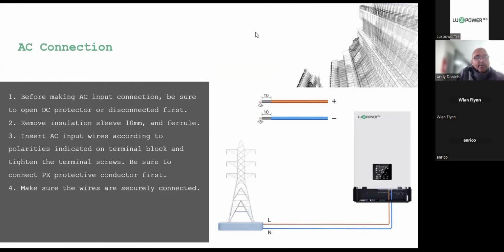All right, so we recommend the right size cable for the application, especially cable that is rated to carry power throughput. Now remember that the throughput power on the SNA 6, I think the rating is 50 amps AC, and we can check that on the spec sheet. So it's always recommended that you use cable, especially from the AC side, through the circuit breaker into the AC in, that is rated to carry the bypass current. Even if you're limiting your output current to 25 or 30 amps, the cable still has to be able to carry the correct current, because when you are AC charging and taking load at the same time through the AC cable, then the cable must be rated to carry the right amount of current.